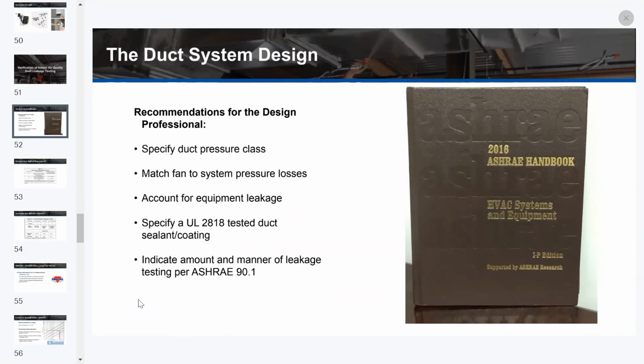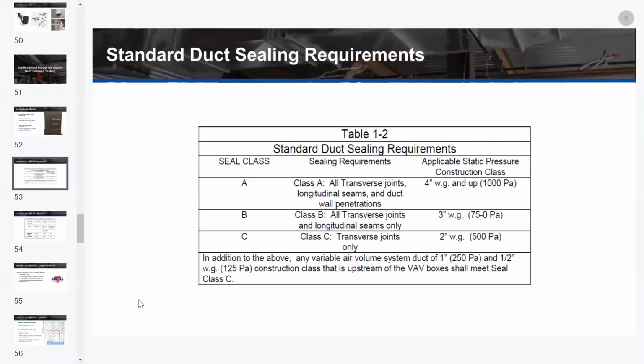To ensure quality control, the designer needs to specify the duct pressure class or classes required for duct construction. In addition, they should match the fan to the system pressure losses and account for equipment leakage, which includes fans, coils, the VAV, etc. They also need to identify the seal class and indicate the amount and manner of leakage testing. And this is where the designer would add to their specification any particular requirements, such as UL 2818 tested and certified for emission levels. It's already laid out and defined in the specs.